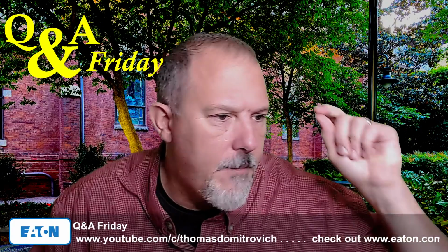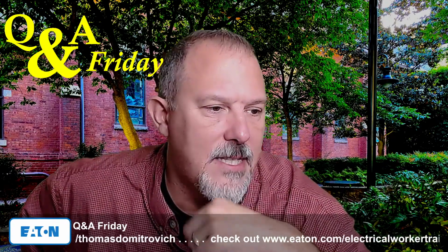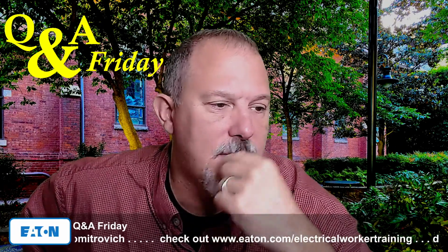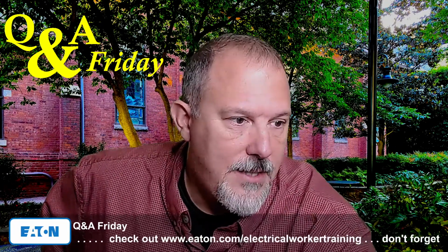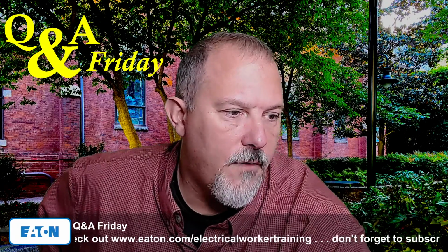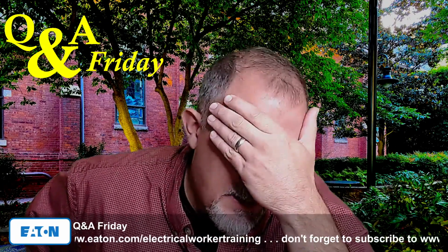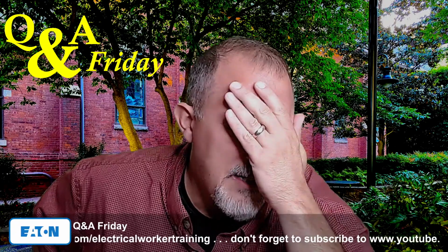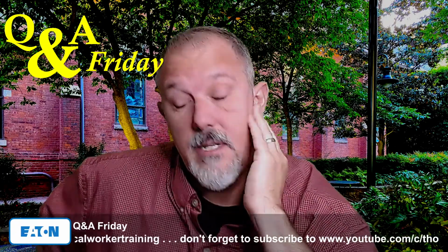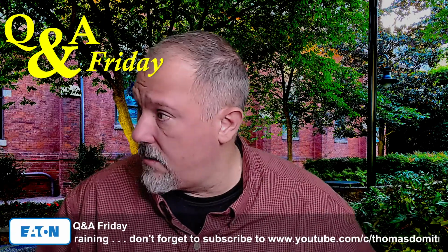All right. Why then can we not use current limiting fuses to protect equipment rated less than the fault current available? Can you address that? And I think I just did. Series ratings are for the assembly only. Robert, series ratings.